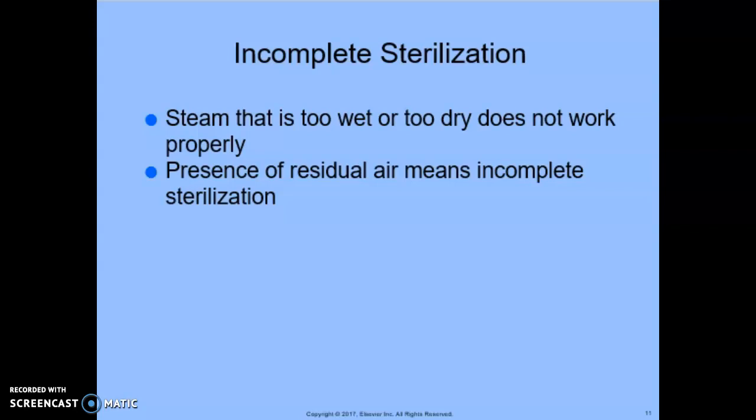Other causes of wet steam include opening the door too wide at the end of the cycle or allowing a rush of cold air into the chamber. Also overfilling the water reservoir. So it's important that you only fill to the fill mark. You can look at table 33.2 for tips to improve the autoclave techniques in your book.